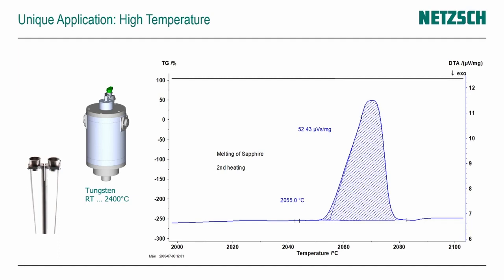The last unique application for the STA is its temperature range. With different furnace options, we can connect a tungsten furnace with a tungsten heating element and measure up to temperatures of 2400°C, allowing analysis of ceramics or high melting metal alloys — which is simply not possible with small tabletop dedicated DSC systems.